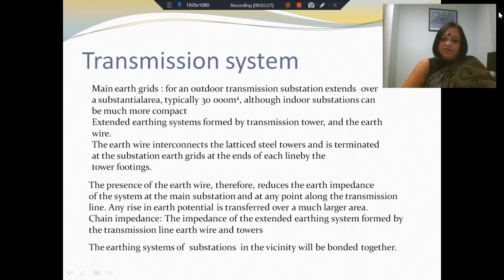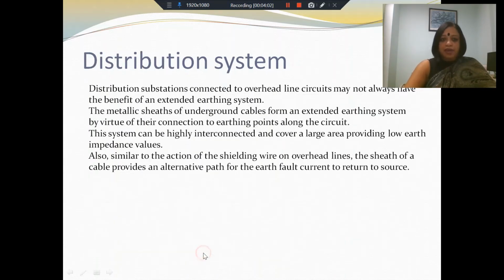The earthing system of substations in the vicinity will be bonded together. Let's say you have a main substation and in the vicinity you have another substation. In this case, you will always try to bond the earthing system of the main substation with the earthing system of the secondary sub-transmission substation. So essentially what we always try to do is extend the earthing system, make it as extensive as possible, and make sure that it spreads over a very large region. So more components and a greater geographical area.